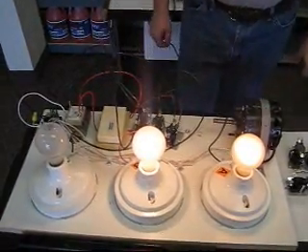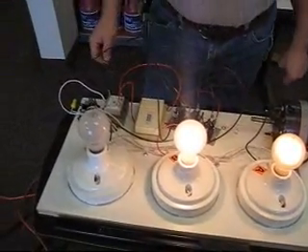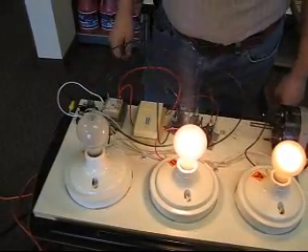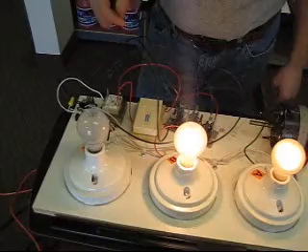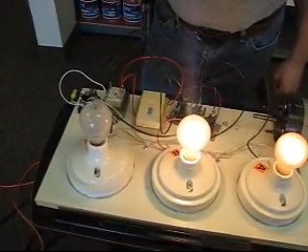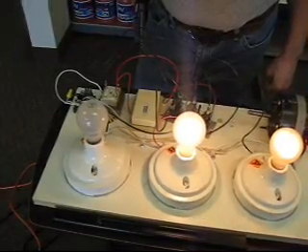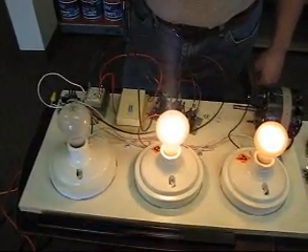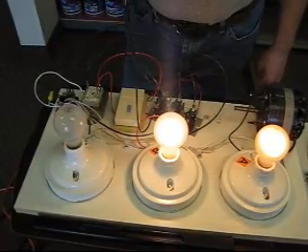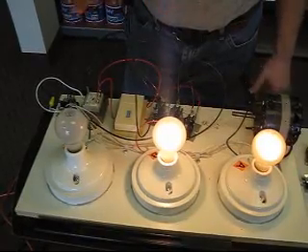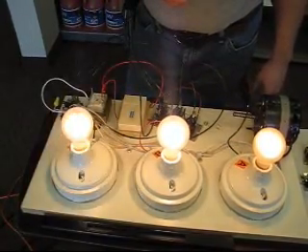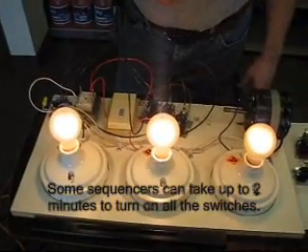There we go. Element number two is on. And then we're going to watch the third element come on. There we go. A lot of sequencers will take almost up to two minutes for everything to come on. And that's typical. Don't get excited if it seems like it's too long.